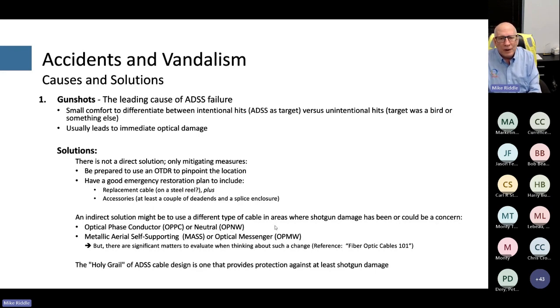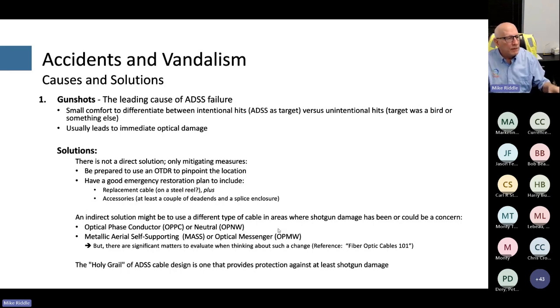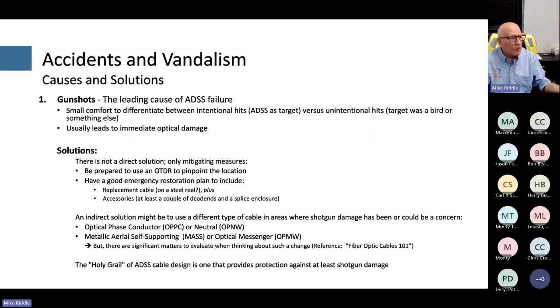Alternative cable types include optical phase conductor, optical neutral for distribution circuits, metallic aerial self-supporting cable, or optical messenger cable. There are significant considerations in using any of these, covered in a previous webinar called Fiber Optic Cables 101. If you know a new circuit crosses a hunting reserve, head that off with a different cable type.